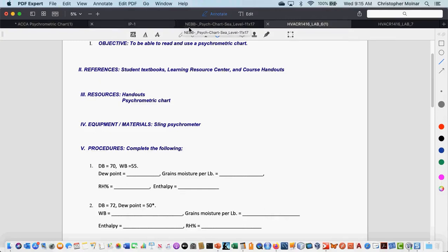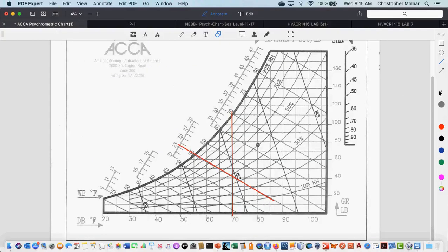If you watched the videos last night, you'll know the dew point uses the same temperature scale as my wet bulb, but it's straight across. So dew point uses the same number as the wet bulb. Wet bulb is at an angle, but my dew point is straight across. In this situation, the dew point is sort of halfway between 40 and 45. So my dew point, I would say, is about 43.